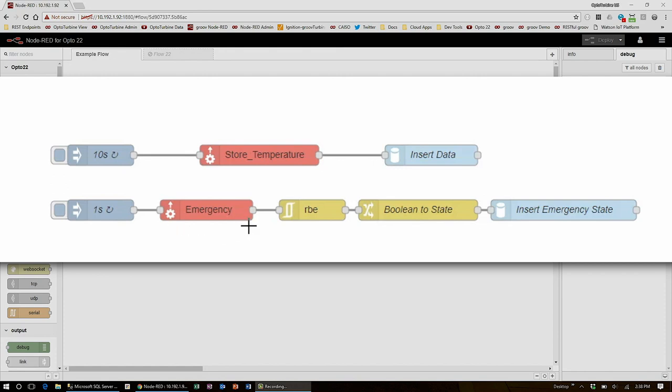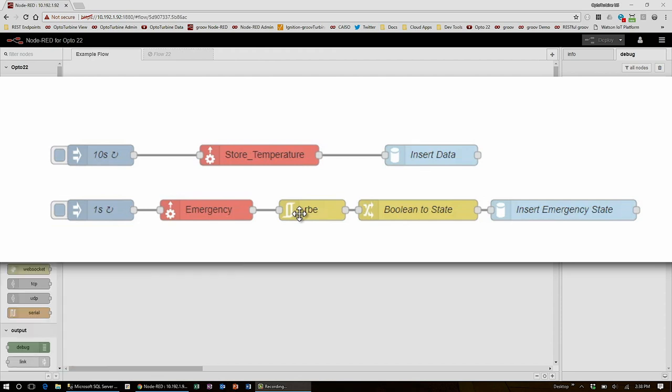Here you can see I already have the store temperature insert set up. My flow every 10 seconds reads in the store temperature and then inserts it into a time series data table in the Workshops database. I also have an emergency alarm state insert that only inserts data when the emergency switch is toggled. I'll add one more I/O point to each table starting with the fuel level to the time series table.